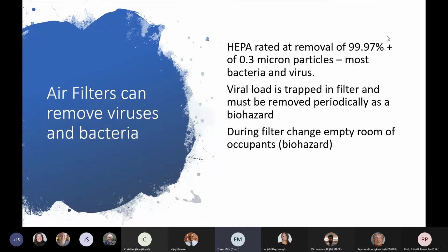So you've got to be very careful when you replace that. You certainly wouldn't replace that with anybody in the room apart from the engineer or technician who's replacing it. So if it's a ward application, you'd have to empty the ward that day, or take the unit out of the ward if it's a mobile and do it somewhere else. During filter changes, treat it as a biohazard.